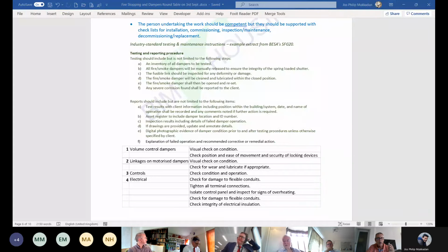That then becomes the question, Paul, as to what would that maintenance person do to do that inspection? And then we get back into the whole competency issue. So it's all very well doing a mechanical check. Anybody can lift a bonnet and check everything's there. Fundamentally, they don't know whether it meets the rules or not. And if they don't know, then you really need to do something about it. And the other point is it might be that it's damaged around the outside. So I don't like to use it, but the installation method, the fire stopping that's used might have been chipped away, or it's not been installed properly, and that's not covered here, and I'm quite shocked.